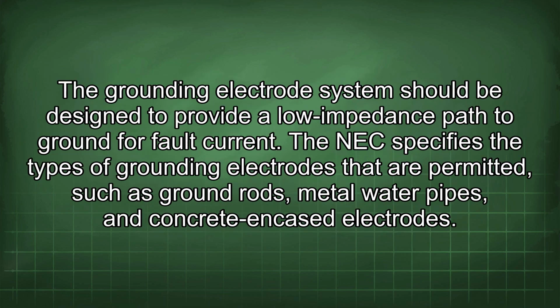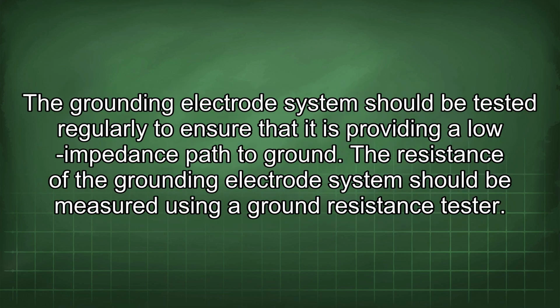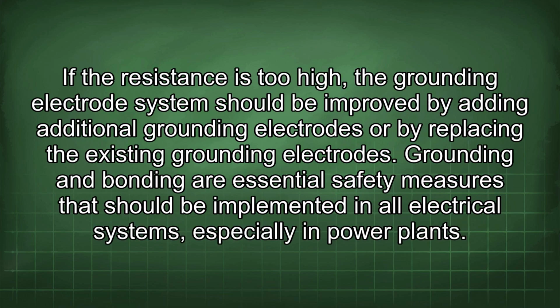The grounding electrode system should be designed to provide a low impedance path to ground for fault current. The NEC specifies the types of grounding electrodes that are permitted, such as ground rods, metal water pipes, and concrete encased electrodes. The grounding electrode system should be tested regularly to ensure that it is providing a low impedance path to ground. The resistance of the grounding electrode system should be measured using a ground resistance tester. If the resistance is too high, the grounding electrode system should be improved by adding additional grounding electrodes or by replacing the existing grounding electrodes.